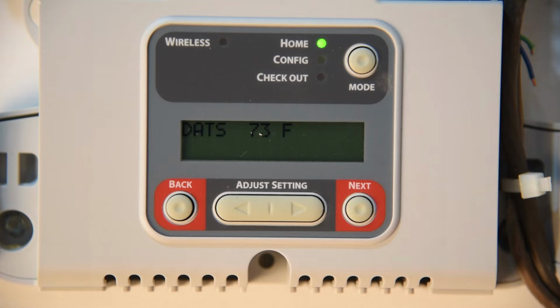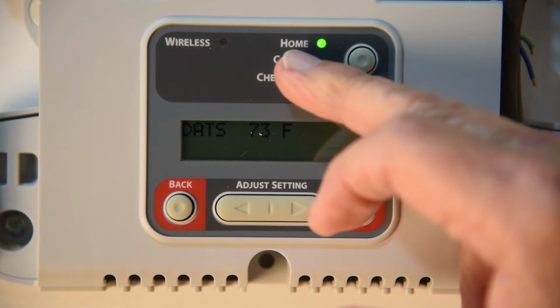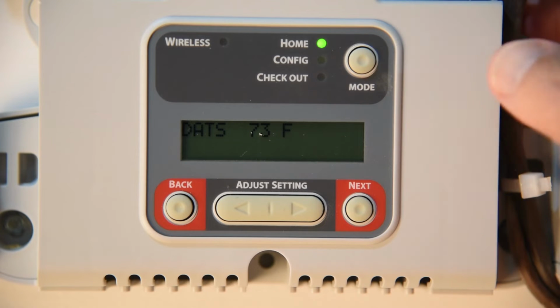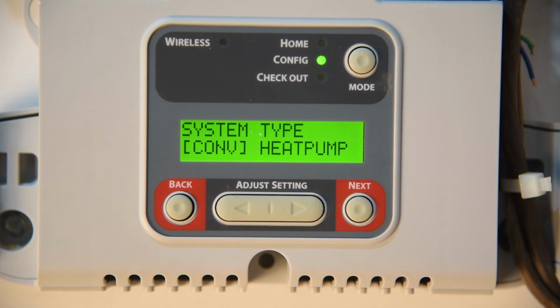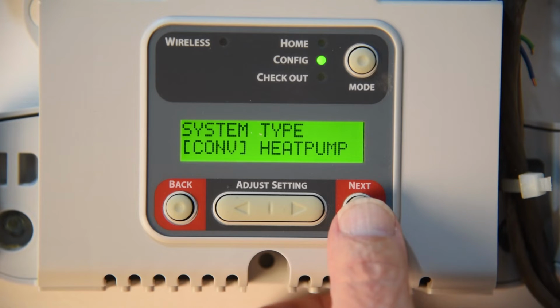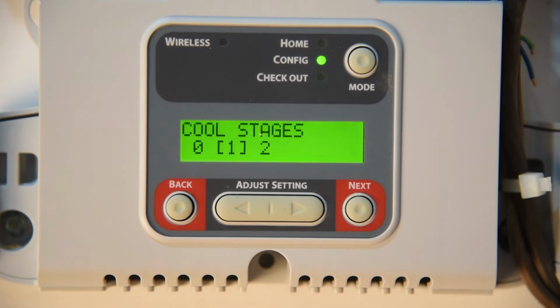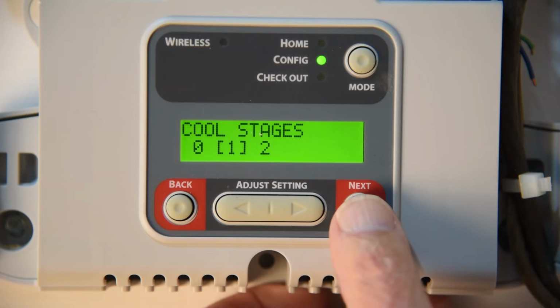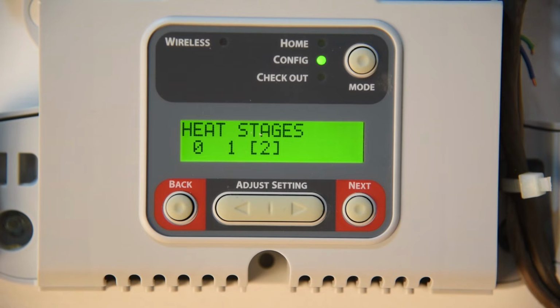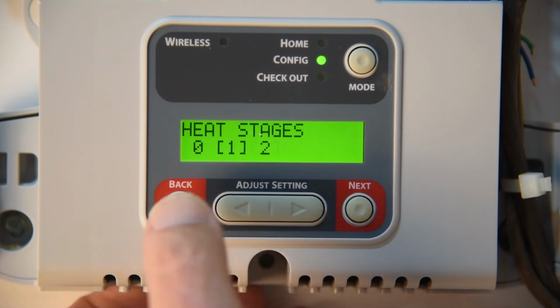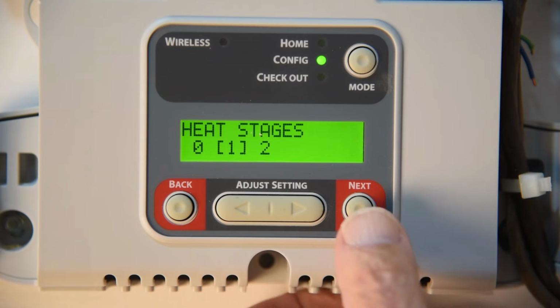Okay, the first thing you're going to do, normal operation, you're in the home mode. You hit mode, and that brings you down to configure. It's going to ask you what type of system you have, either conventional or heat pump. Well, in this case I have conventional, so I'm going to hit next. Now, the next question is, how many stages does your equipment have for cooling? I have 1. You can set it at 0, 1, or 2. I'm going to hit next. How many heat stages? Well, I have 2, but if you only have 1, you can move it down to 1. I'm going to hit next at 1.